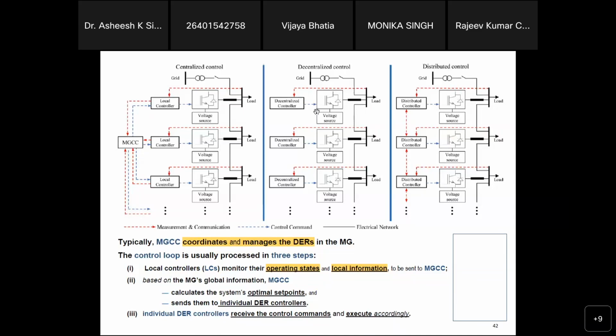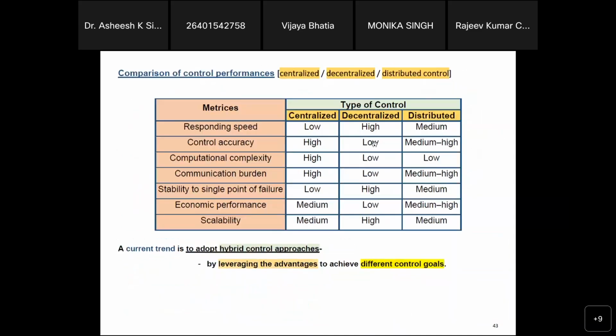They may not have interconnections, and they perform calculations of required data and decision making at their local level. That is why, when comparing these metrics for different types of control, we can conclude that the responding speed is lowest for centralized control, highest for decentralized control, and medium for distributed control, since there is communication between decentralized and distributed controllers.